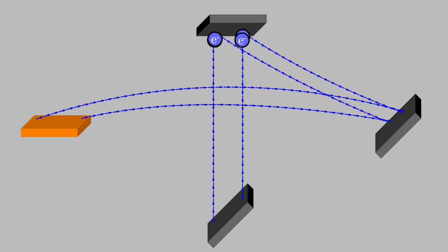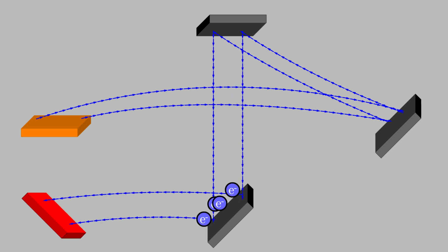This chain reaction is arranged one after another. At the end of the chain, there is an anode that collects all these electrons. This massive collection of electrons creates an electrical current. When this current flows through a resistor, it generates a measurable voltage pulse. By reading this pulse, we can determine exactly how many photons arrived and when they arrived. This is the overall logic of photomultiplier tubes.